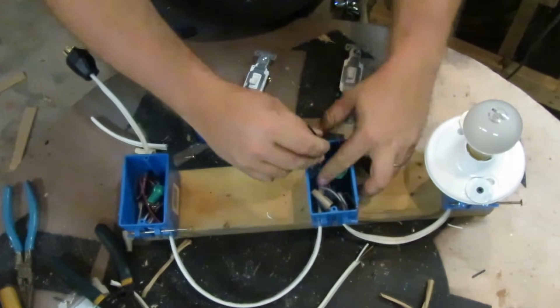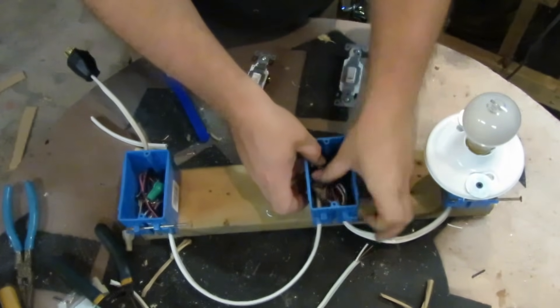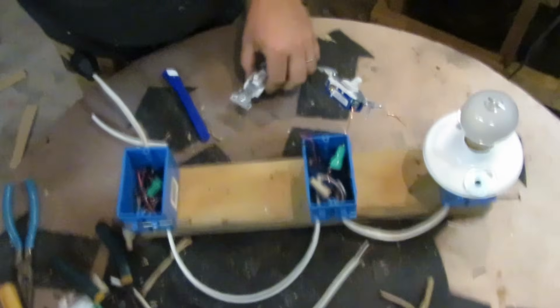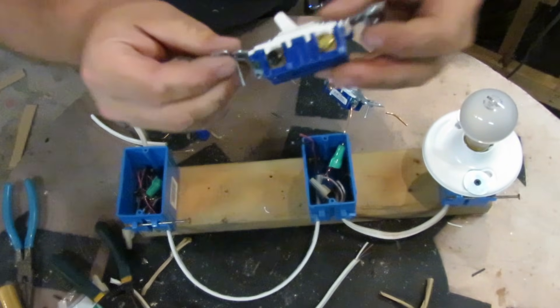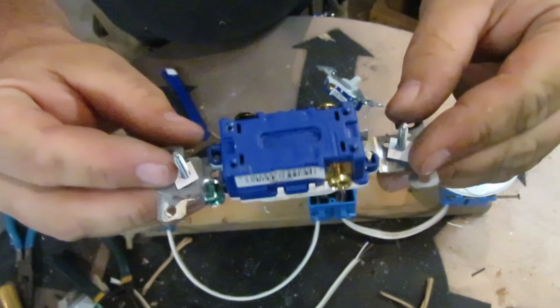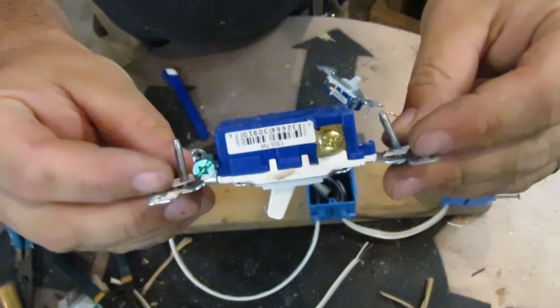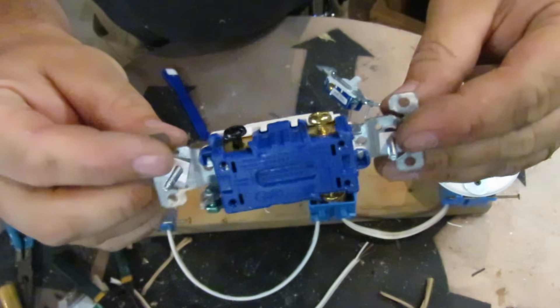And well, this is our three-way switch. It has two brass screws and a black screw. Now the brass screws are for the travelers, you put one to each, and the black screw is the common.